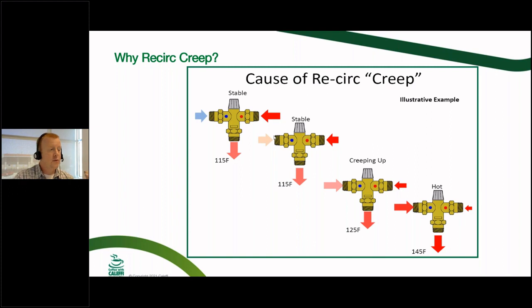But then sooner or later, everybody goes to bed, or the demand from the potable system or domestic hot water system goes way down, and sooner or later the mixing valve is just working with the really hot temperature from the domestic hot water source and the pretty warm temperature from the domestic hot water recirc. And so the mixing valve can handle this for a certain amount of time. It's going to try and do its job the best it can, and you'll notice it's still maintaining.